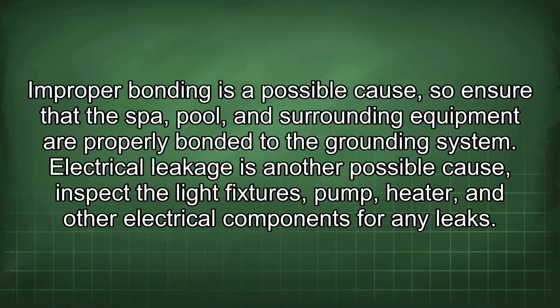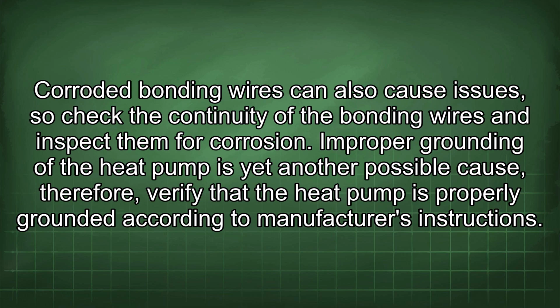Improper bonding is a possible cause, so ensure that the spa, pool, and surrounding equipment are properly bonded to the grounding system. Electrical leakage is another possible cause. Inspect the light fixtures, pump, heater, and other electrical components for any leaks. Corroded bonding wires can also cause issues, so check the continuity of the bonding wires and inspect them for corrosion.